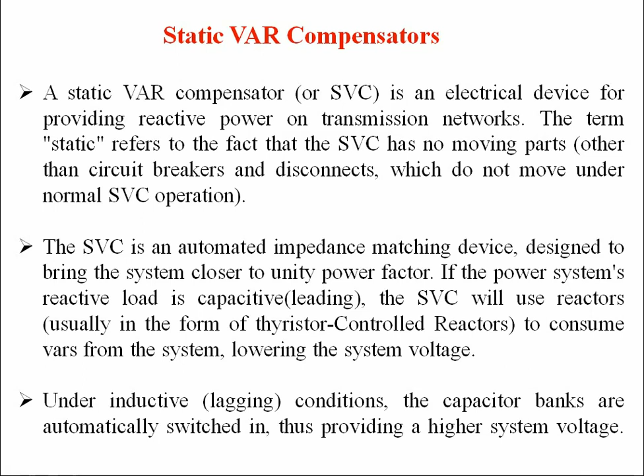So it can work both ways. Under the leading or capacitive condition, it will use the reactors to consume the vars, and during the inductive, that is lagging, conditions, the capacitor banks are automatically switched in, thus providing a higher system voltage. This lowering and increasing of the system voltage as per the requirement is done by this SVC, and this is what we call providing compensation. So this one is the static var compensator.